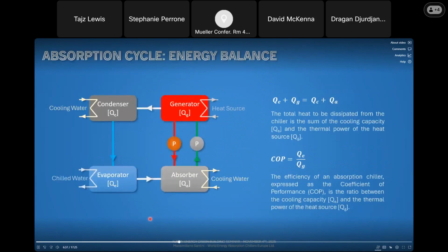The total heat to be dissipated from the absorption chiller is the sum of the cooling capacity, so the evaporator thermal power, and the thermal power of the heat source. The heat is dissipated using the cooling water that circulates in both the absorber and the condenser heat exchanger. The efficiency of an absorption chiller, expressed as the coefficient of performance, COP, is the ratio between the cooling capacity, so the evaporator thermal power, and the thermal power of the heat source, so the thermal power of the generator heat exchanger.